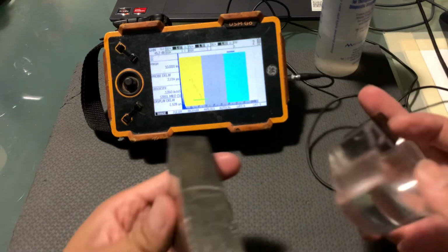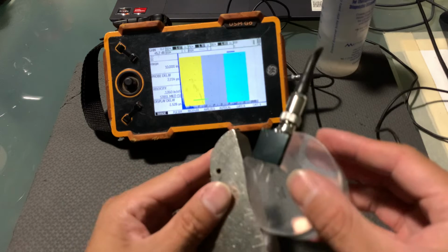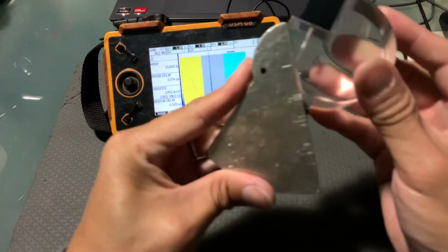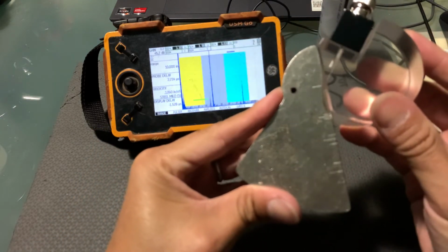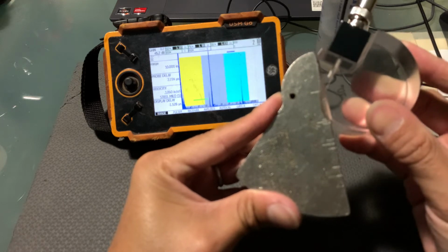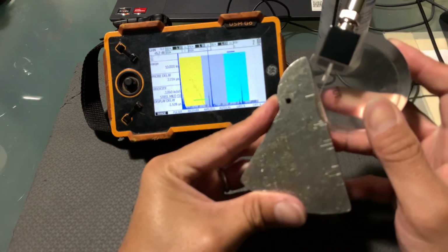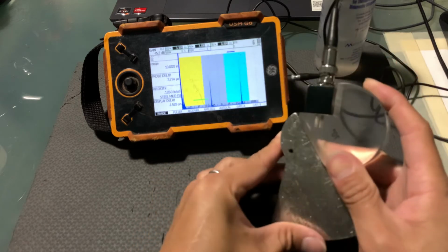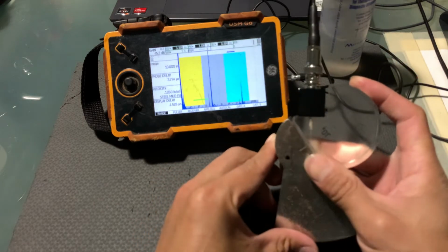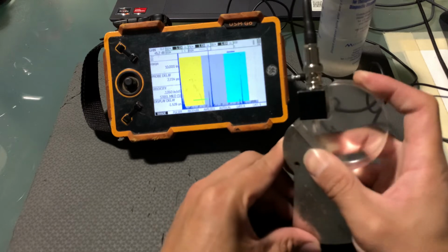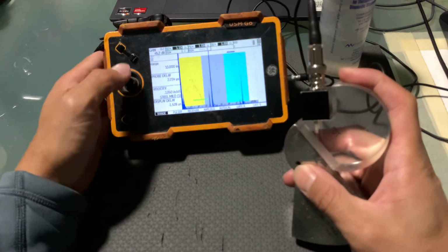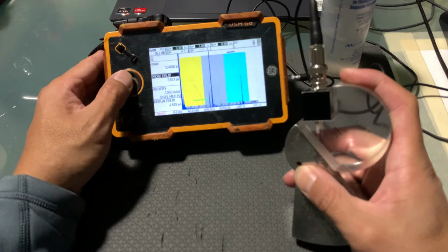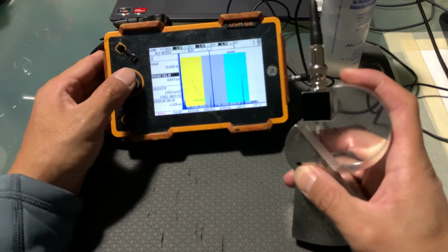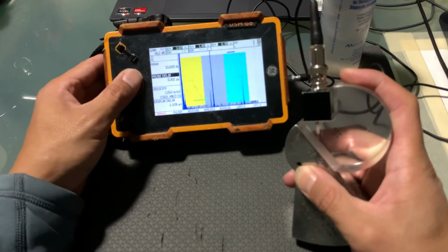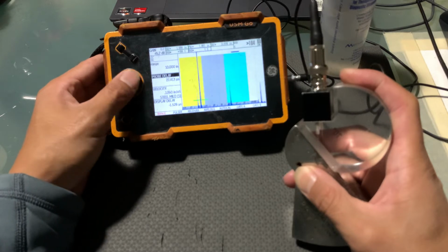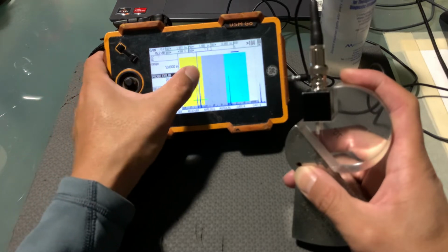Next, we're going to go distance. So we're going to go to the other side. We're going to line up that mark there from the very end. And notice how our back reflection is not at 3 inches. So what we're going to do is move the probe delay until the distance is at 3 inches. So 1, 2, 3.